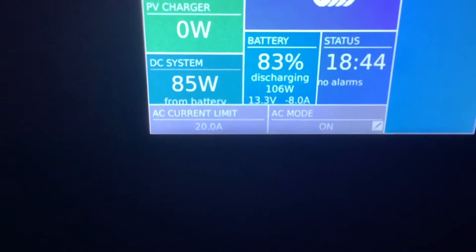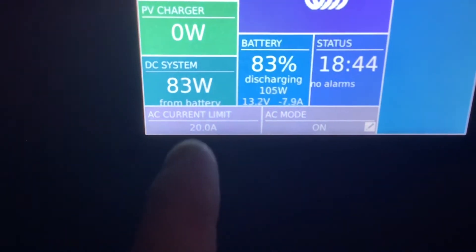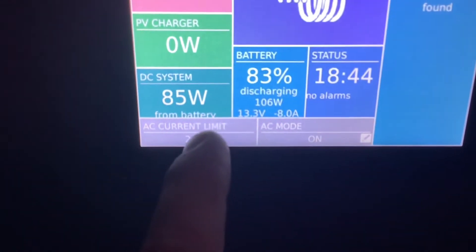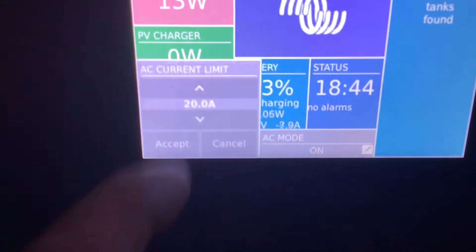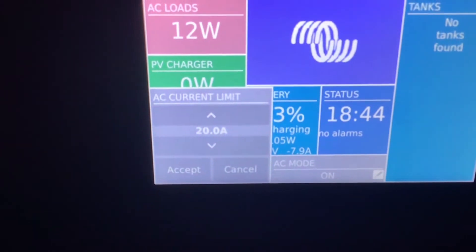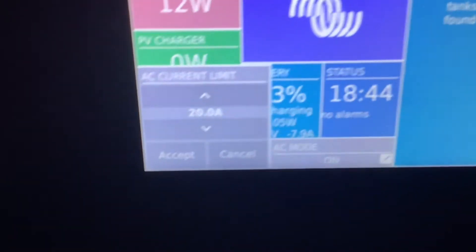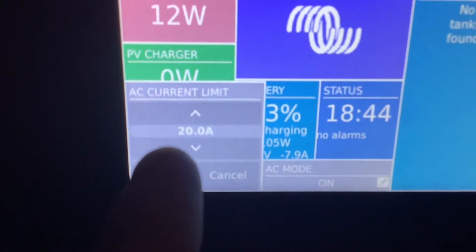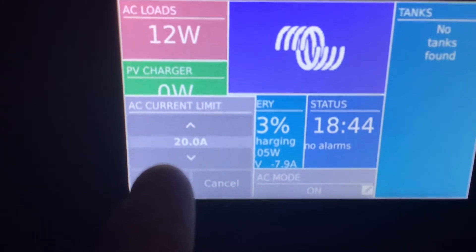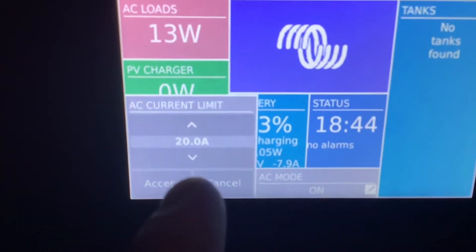This number lets the inverter know how much shore power you have to work with. If you use more than the shore power can provide, the solar and the batteries will pick up the rest of it.